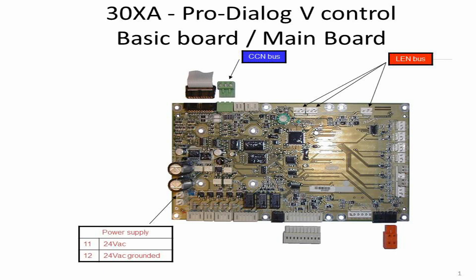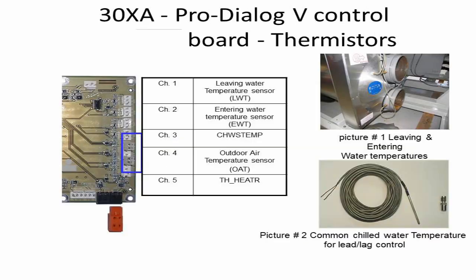CCN stands for Carrier Control Network. The top, middle, and left side of the board shows the connection for LEN communication bus. The leaving water temperature sensor is connected on Channel 1 on the baseboard. The entering water temperature sensor is connected on Channel 2. The chilled water system temperature sensor is connected on Channel 3.